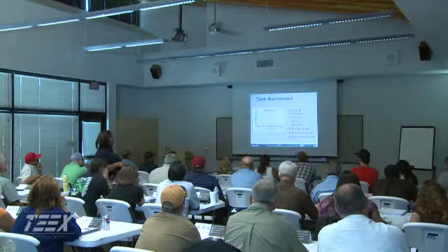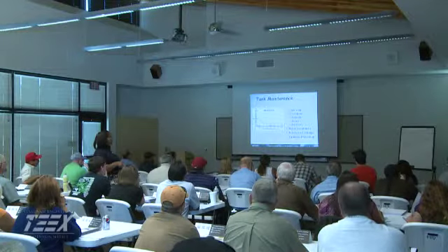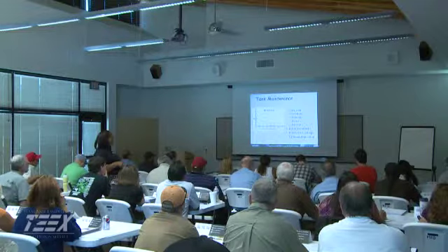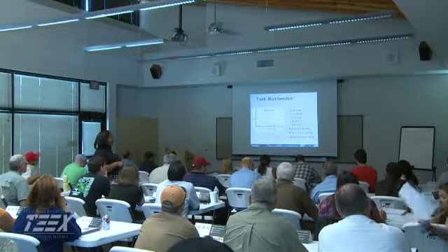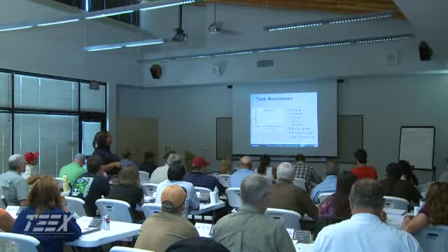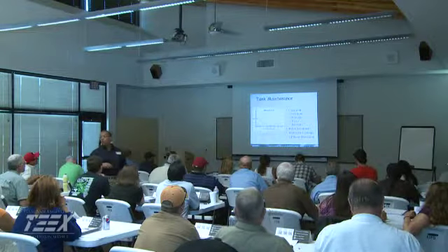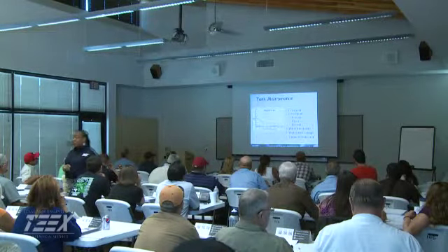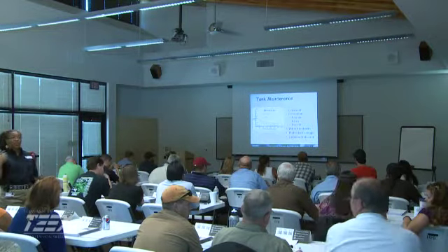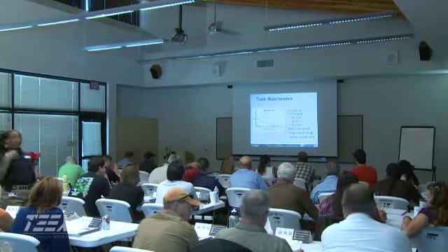For instance, let's say a pH of 7, but my alkalinity is about 250. Now I'm in the stable area, but as alkalinity goes up, it becomes scale forming. If I have very low alkalinity at a pH of 7, and my alkalinity is under 150, my water will be very corrosive. So this can be, again, process control, one of the first things that I can utilize in order to determine if my water is scale forming or corrosive.